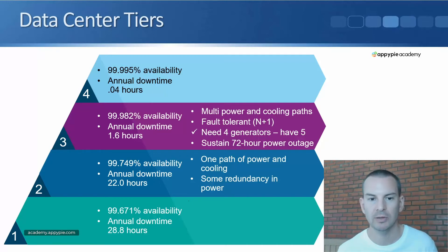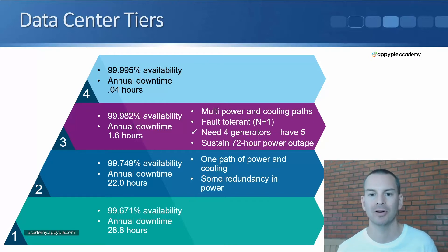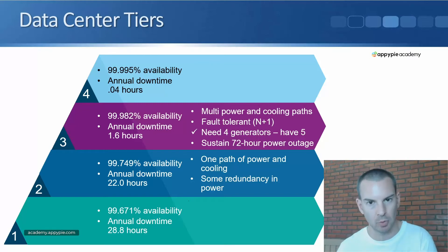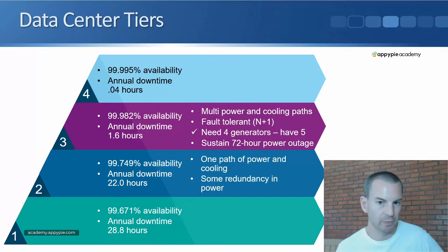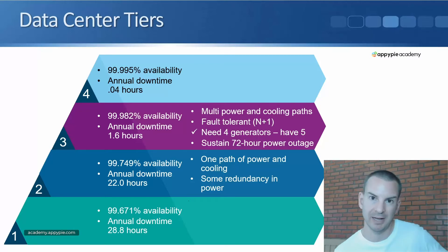Moving up, a tier three data center has an annual downtime of only 1.6 hours. It is required to have multiple power and cooling paths and needs to support N+1 fault tolerance. N+1 means, for example, if you required four generators to supply the required power, you would put in five — you would put in a spare. With the power, it needs to be able to sustain a 72-hour power outage from the grid and still be able to provide backup power from generators.